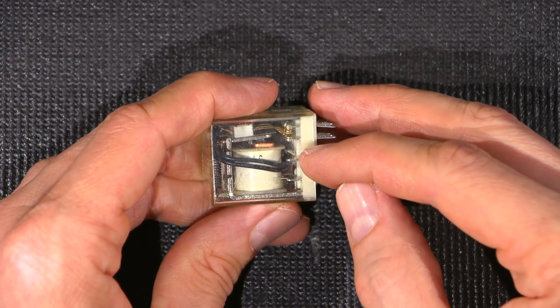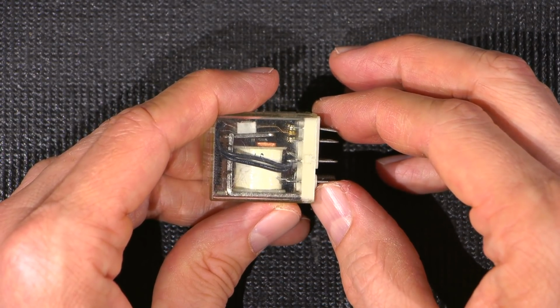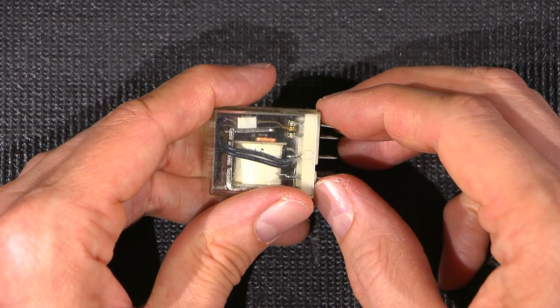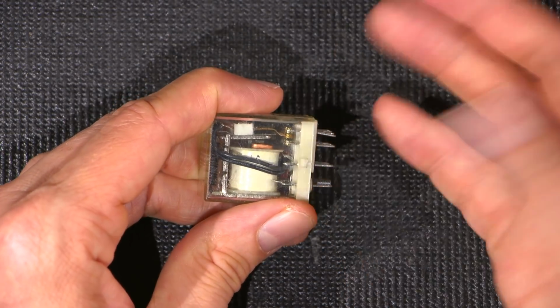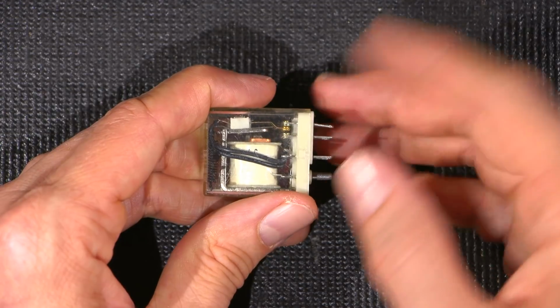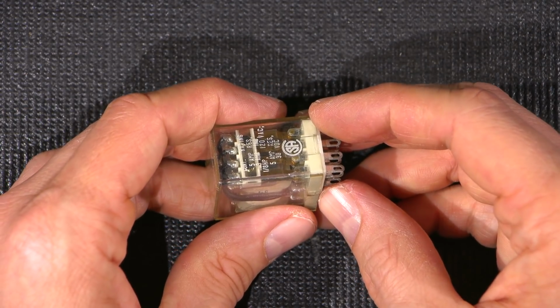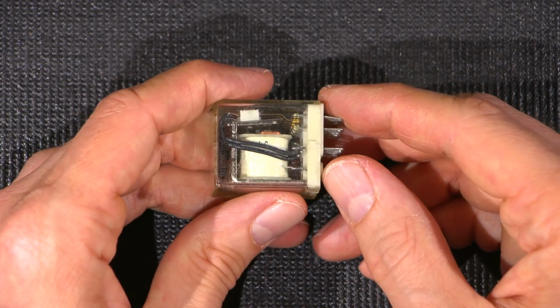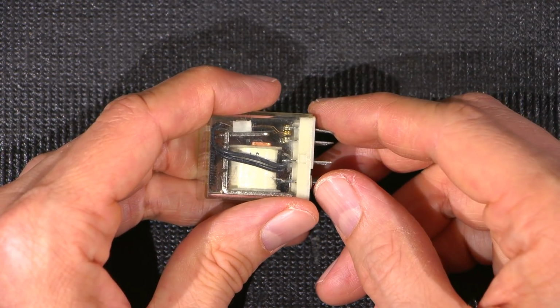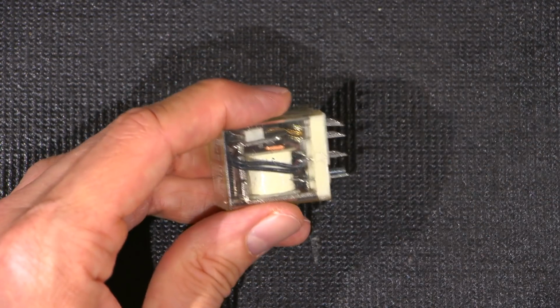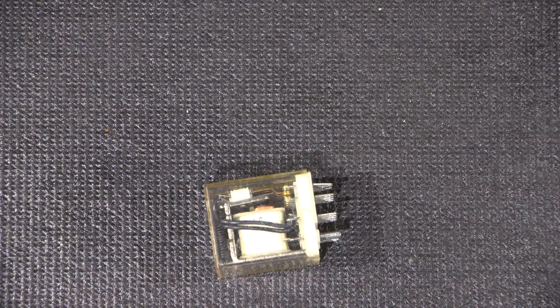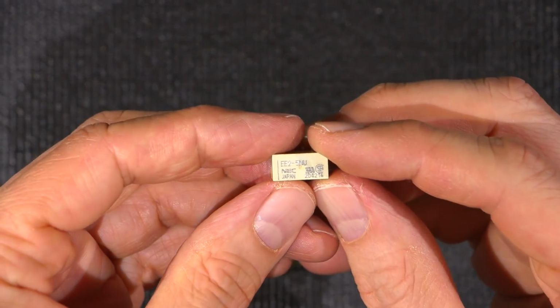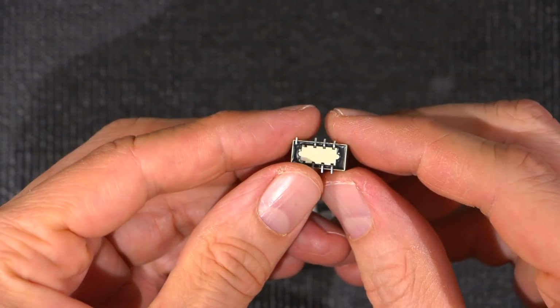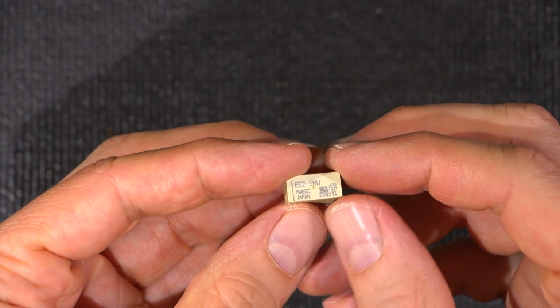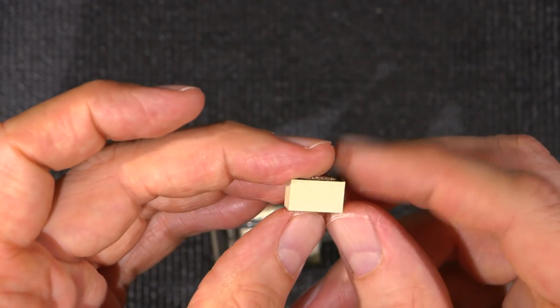So if you have a big relay like this and it's not really passing any type of current, you're going to find that the connection in the relay will get intermittent after a while, whereas if it was sparking and passing current, it doesn't. Again, the actual sparking is a continual cleaning process in relays. Now, unfortunately, this cleaning process in the relays wears the contacts as it's doing it. Passing current does that. You'll find that a lot of small signal relays, and one of those would be right here, are completely sealed up, and they're like this for a reason, so that everything inside is basically no atmosphere inside, and you need that to keep the contacts clean.